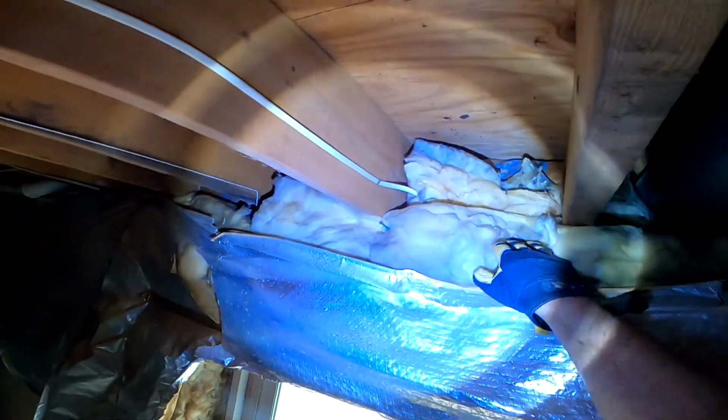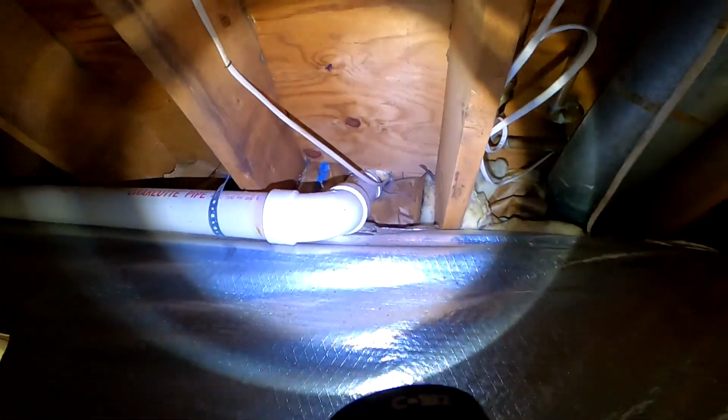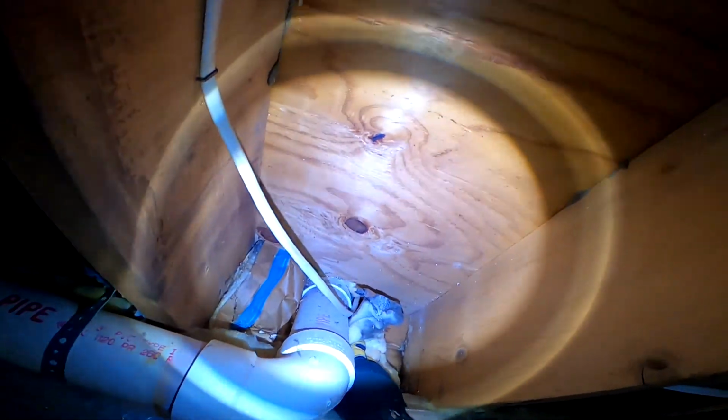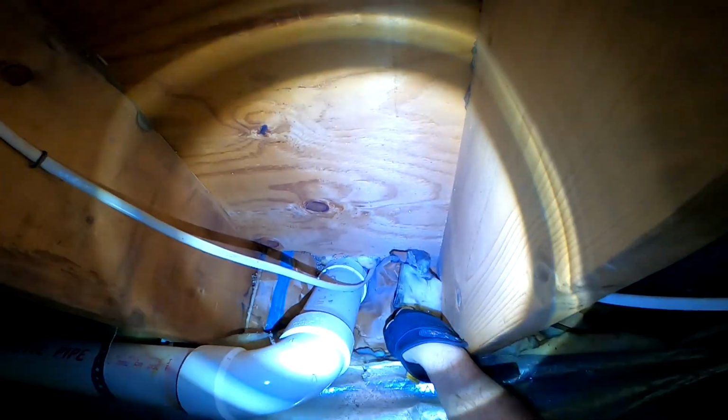On the other side here, you can see, when I pick this one piece of insulation up, how dark and discolored it is, just indicating that that particular area is particularly leaky. And I also wanted to give you another relationship between the overhang and the normal part of the foundation wall that is more flush and near the edge of the wall. And you can see there, again, telltale signs that air is flowing through.